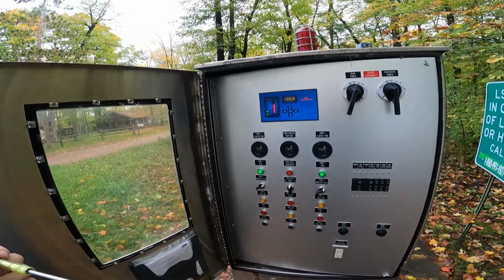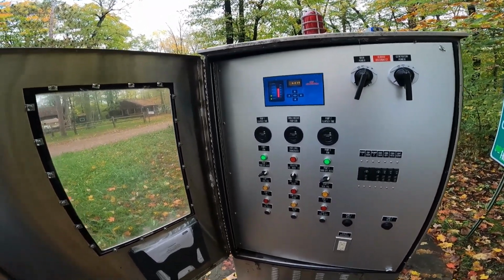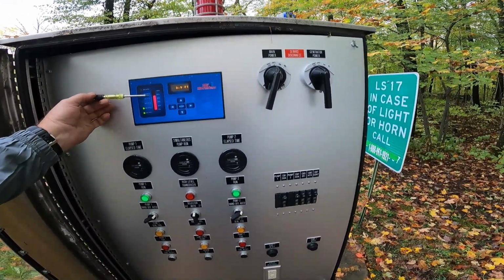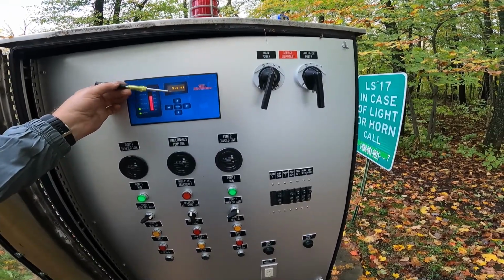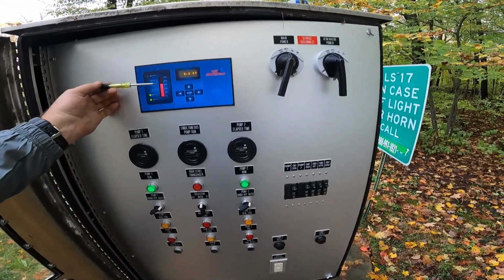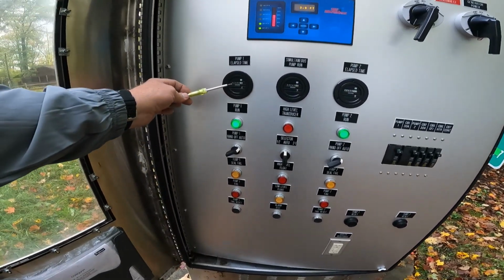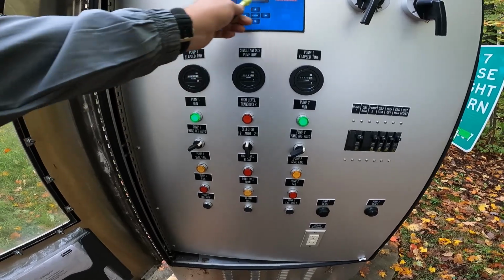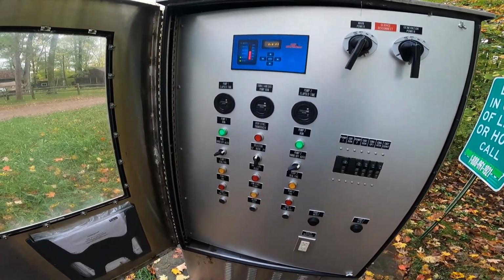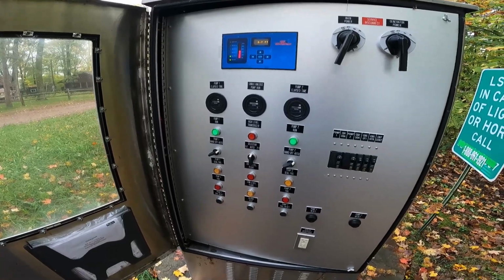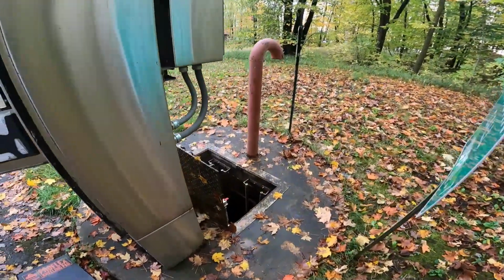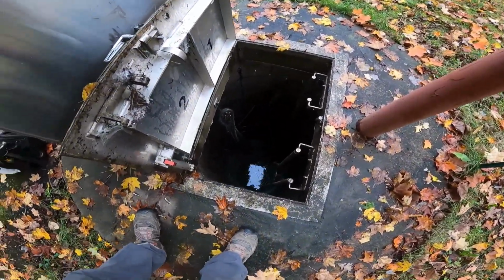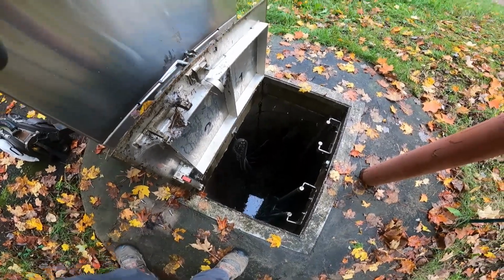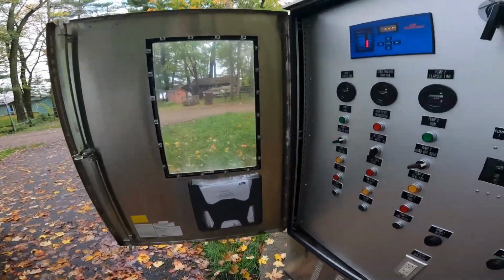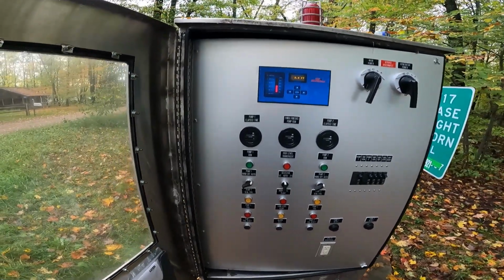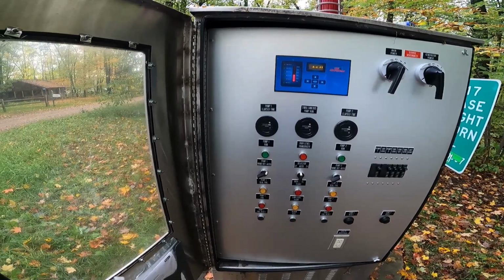I connected that ground that was loose, and now we see the lift station is up at almost 4 feet, which we believe, and now both pumps are running, this one and this one, because it's in a high level. Now we're going to watch and wait and see if this settles down. Let's go look in the tank. And now we got to the shutoff point, 2.5 feet.